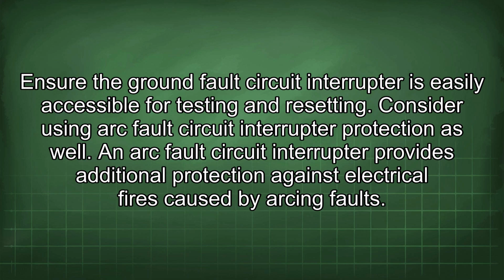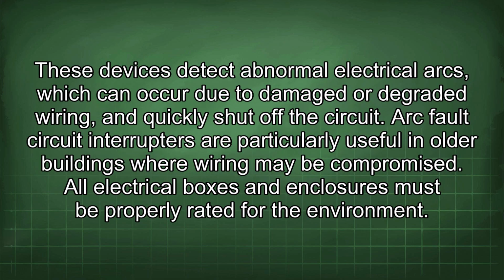Consider using arc fault circuit interrupter protection as well. An arc fault circuit interrupter provides additional protection against electrical fires caused by arcing faults. These devices detect abnormal electrical arcs, which can occur due to damaged or degraded wiring, and quickly shut off the circuit. Arc fault circuit interrupters are particularly useful in older buildings where wiring may be compromised.